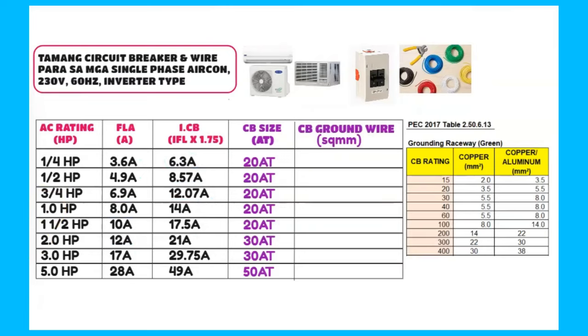Okay, recall lang kanina. So from the table dun sa circuit breaker, inverse time circuit breakers, so meron tayong 20 ampere trip from 1/4 HP to 1 1/2, then 30 ampere trip for 2 and 3 HP, and then 5 HP, that is 50 ampere trip. So this time we'll find out so anong magiging size ng ground wire natin. From the PEC 2017, 2.50.6.13. So ito yung ating grounding raceway.